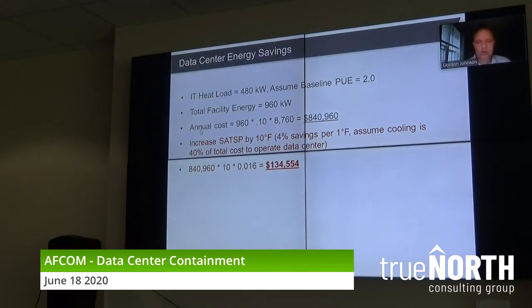In doing this for 9 years now with our company, I don't see 4 or 5%. I see approximately 1.6% as my typical average. Sometimes a little higher, but 1.6 is conservative. It's a fair number. Another way to look at 1.6 is to take 4% savings for every degree, but just look at the cooling of your data center. If I assume the total cost of cooling is 40% of the total cost to operate your data center, it breaks down to 1.6%. So that's the number I like to go with.